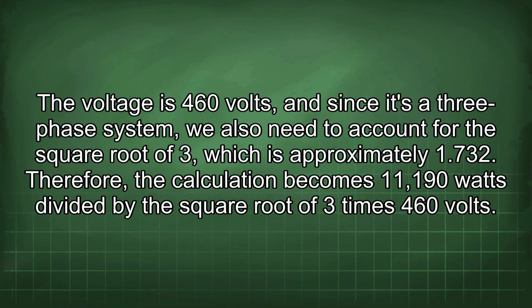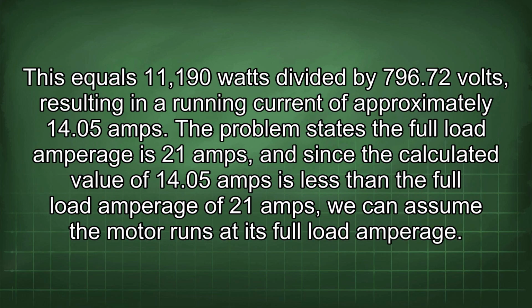square root of 3, which is approximately 1.732. Therefore, the calculation becomes 11,190 watts divided by the square root of 3 times 460 volts. This equals 11,190 watts divided by 796.72 volts, resulting in a running current of approximately 14.05 amps.